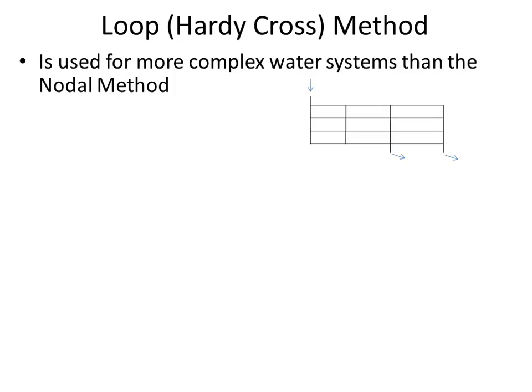And if so, then we'll move a little bit of water through a different pipe and then check the energy balance again. And the nice thing about this is that when I said we'll move a little bit of water from one pipe to another, we don't have to manually interact and do that. There is an equation that will make the correction for us. It automatically makes the correction so that once we set up the spreadsheet, we can just copy and paste multiple times, and it'll just sort of automatically converge on the right solution. And so that's what we really like.